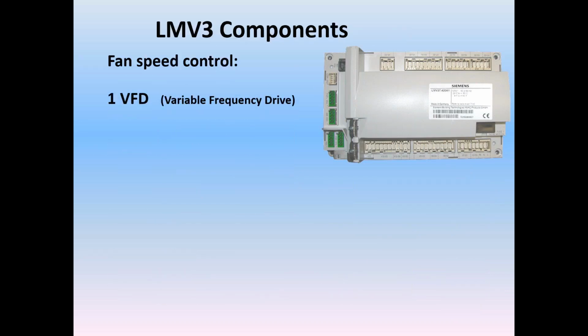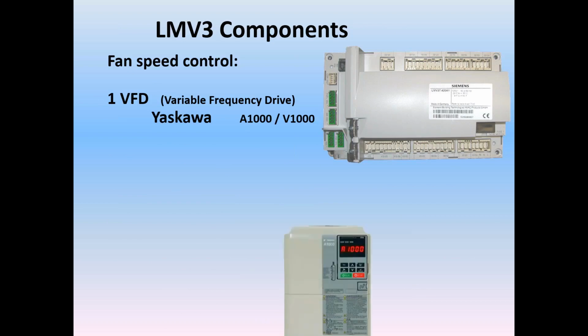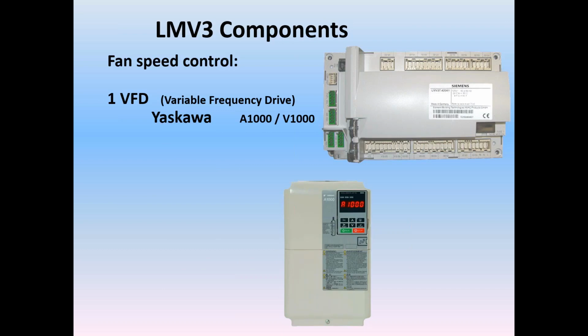For fan speed control, the first option is a variable frequency drive. Variable frequency drive, SCC out of Chicago, we sell Yaskawa drives, or we give you the programming you need to do Yaskawa drives. A1000, V1000 series are vector drives. And then you would have to add a speed sensor to your motor.